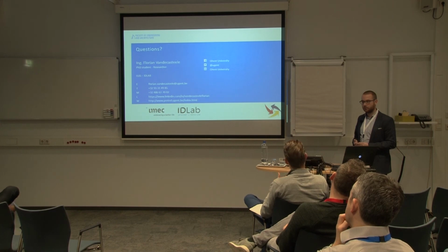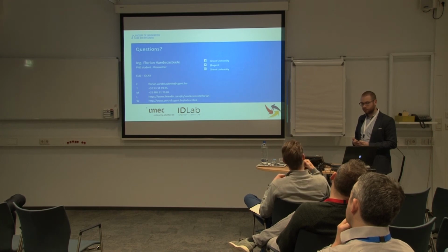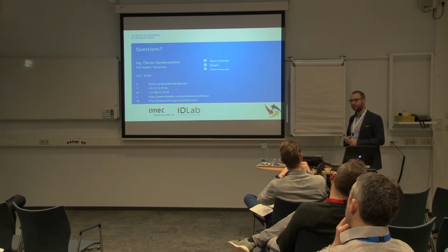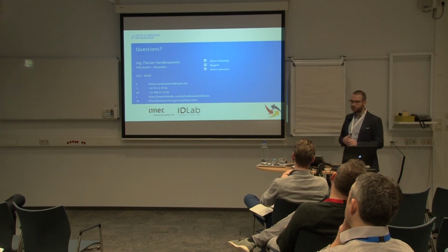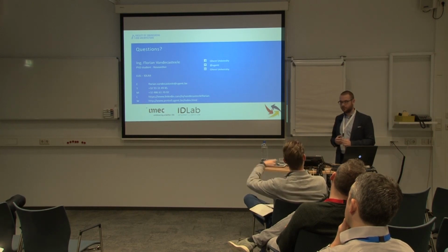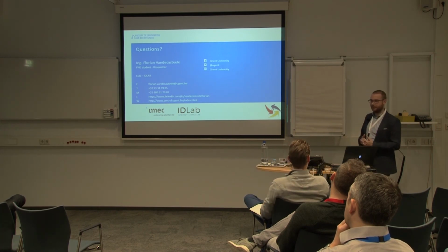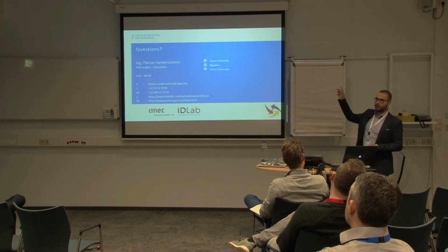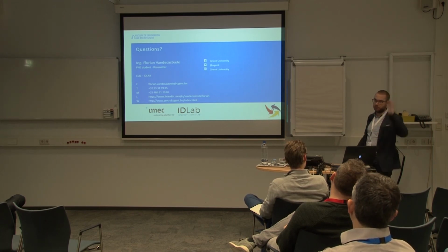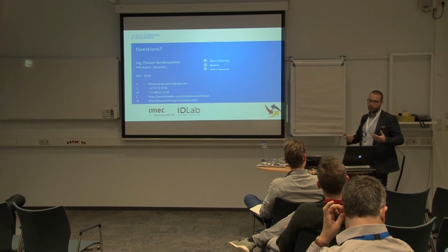This morning we saw cameras can see through objects. You said you have 20 cameras inside of the tunnel. In your machine learning algorithms, your image recognition, do you have trouble finding out what the height is? Smoke height or fire height? When there's a difference in distance from that layer. So that's a bit the problem. When you look at CCTV cameras, they are always placed on the ceiling. But yeah, that's a problem, and you can't see.